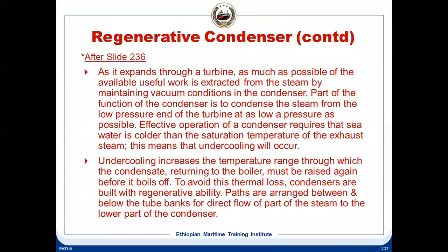Quite true. Effective operation of a condenser requires that seawater is colder than the saturation temperature. Let's say we consider the steam which is coming out at atmospheric pressure, just for the sake of argument. At atmospheric pressure, the saturation temperature of steam, that is your boiling point, is 100 degrees centigrade. It follows that the seawater or the cooling water should be colder than 100 degrees centigrade for the condensation to be carried out properly. But it also means that undercooling will occur.